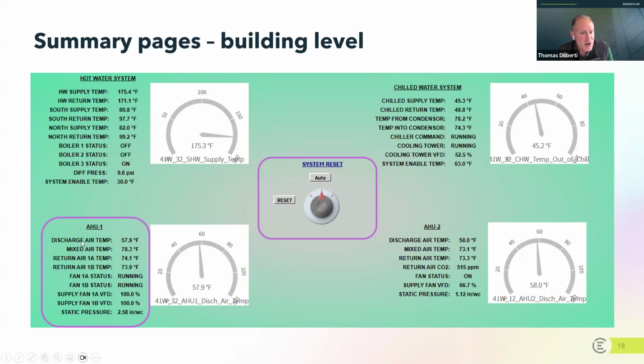For this air handling unit, the discharge air temperature is saying the temperature going into the space is roughly 58 degrees. Well, for this type of air handling unit where it has mixed air, there's a hot duct and a cold duct that come together to mix the air. So if the mixed air temperature is 78 degrees, it's a little bit surprising that the discharge air temperature would be so dramatically different. So this might be a sensor issue. It's just an inconsistency with how I'm viewing this. Also, the return temperature coming from a couple of different spaces for this air handling unit is pretty comparable, which means the air coming back, which for many organizations represents the actual temperature in the space, is about 74 degrees. So again, something might be a little bit weird here, but this is giving a nice consistent 74 degrees coming back from the space.